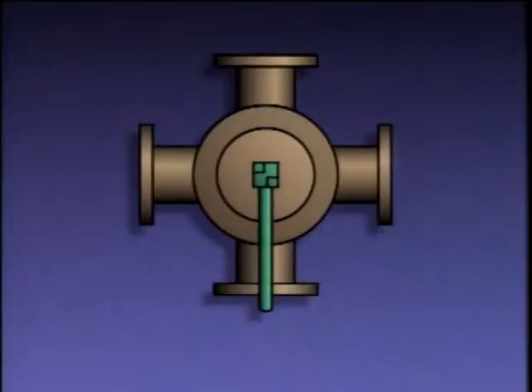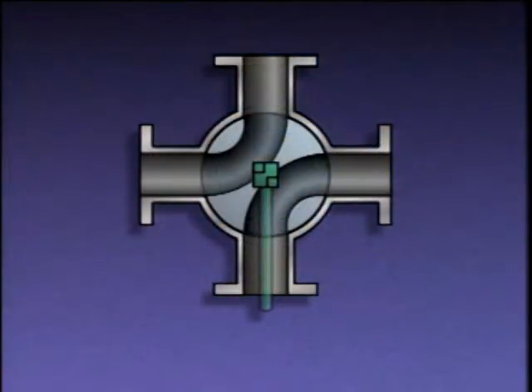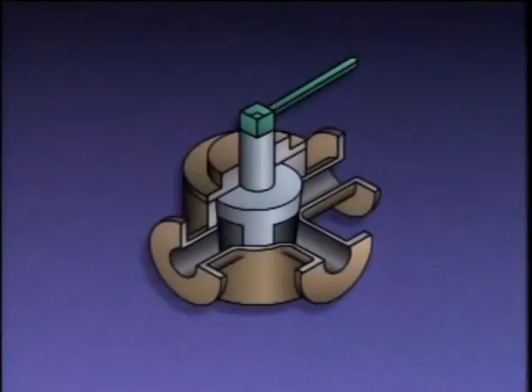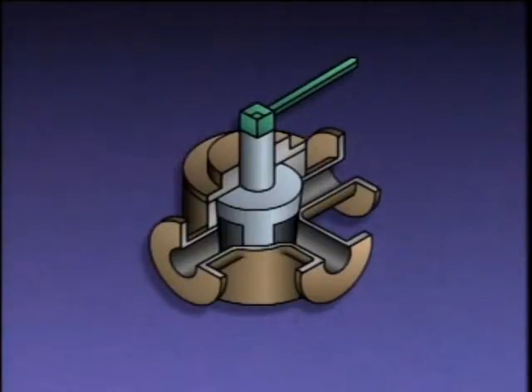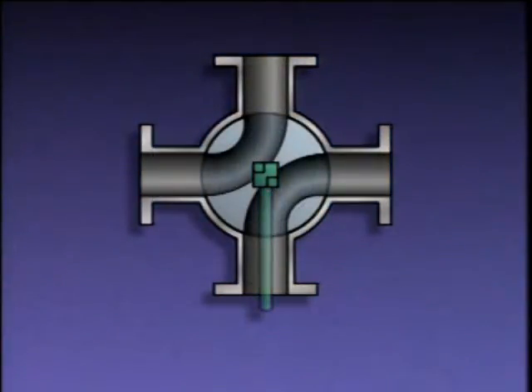Some multi-port plug valves have more than one L-shaped opening. A plug valve with two L-shaped openings is called a four-way valve, commonly used to change flow through a piping system. Multi-port plug valves usually have L-shaped markings on their handles to indicate valve position — three-way valves have one L and four-way valves have two, so the direction of flow can be determined by comparing the L positions to the piping.